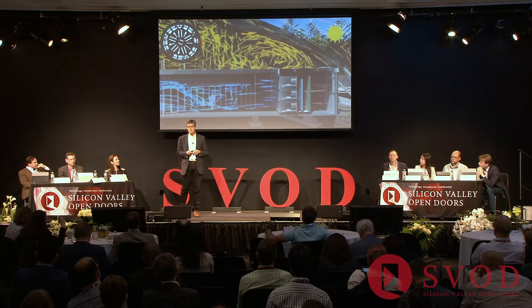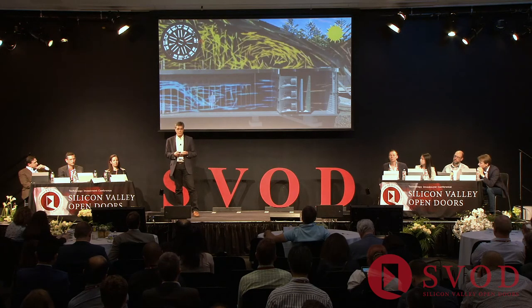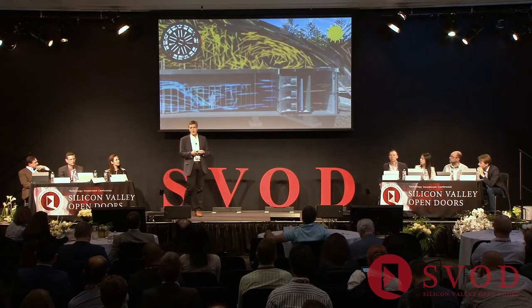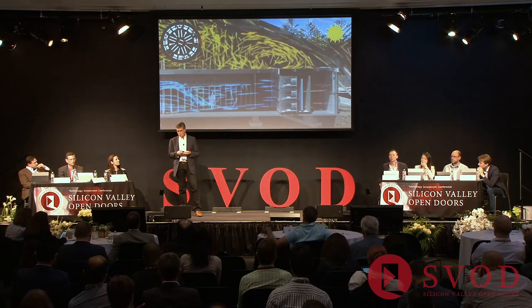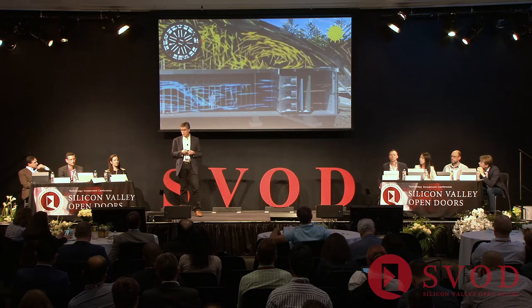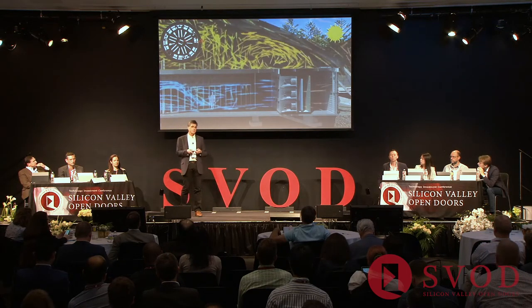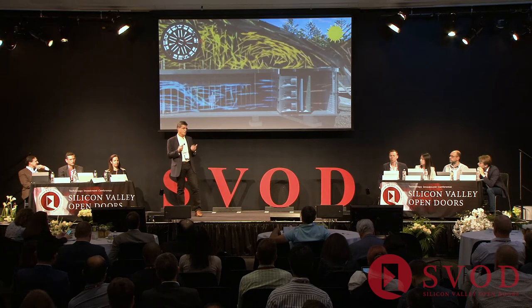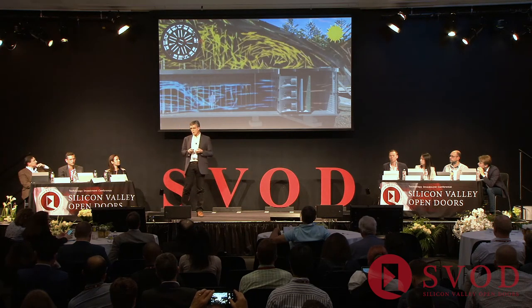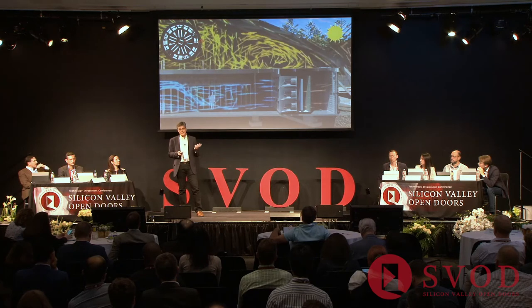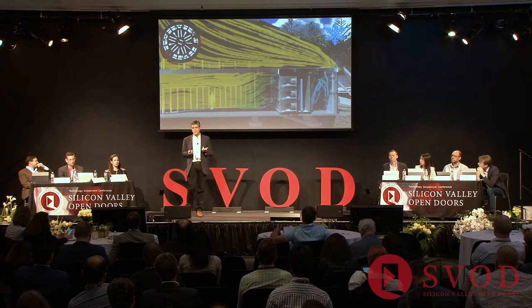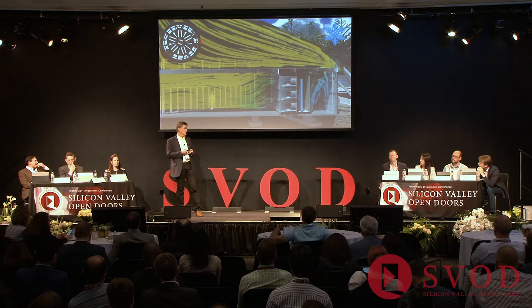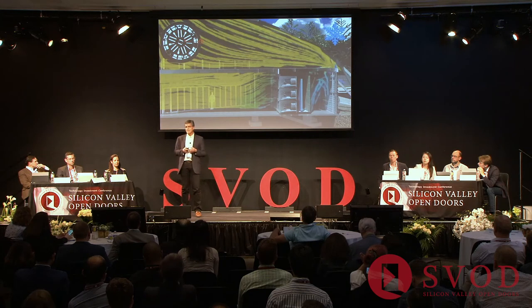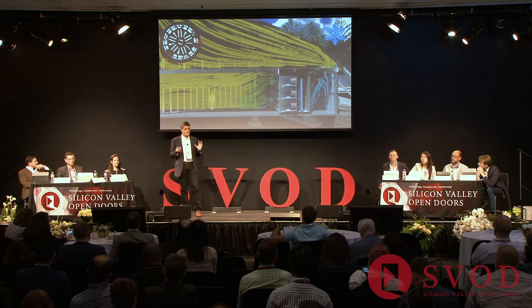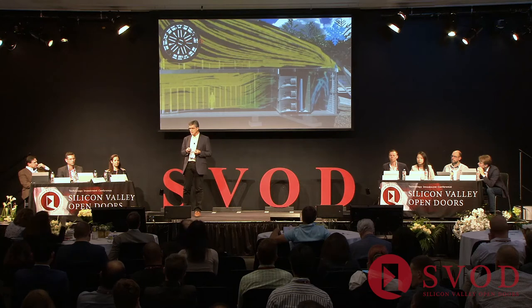Unlike most data centers, we have no mechanical systems, no refrigeration, no chillers—all ambient air cooled. As you can see in the blue, there's air blowing through fan walls, then through the servers, and the yellow depicts the warm air rising and then being exhausted. In the wintertime, the airflow is different because we use that to heat and keep a constant set point in the data center. This is unlike any data center out there, arranging all the pieces in a very unique and patented design.